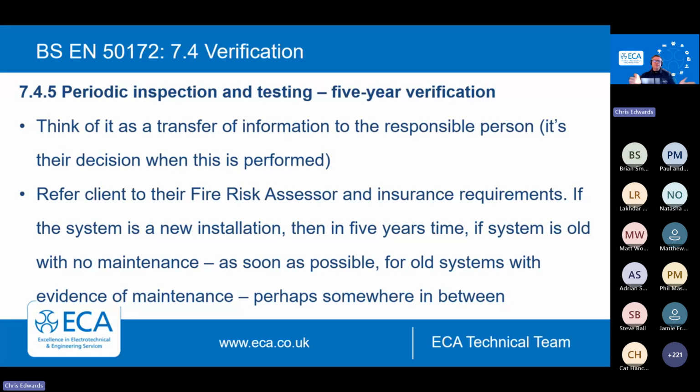But consider it like this. If the system is a new installation and it's got its initial design, then of course it's 5 years' time. If the system is old with no maintenance, really ideally as soon as possible. For old systems with evidence of maintenance, somewhere in between. All we can do is offer that information to our client. It's not a pass or fail thing, and we need to be careful about what sort of information we're imparting. It's not like you must do it. The requirement is theirs. Give them the pointer. It's their responsibility.